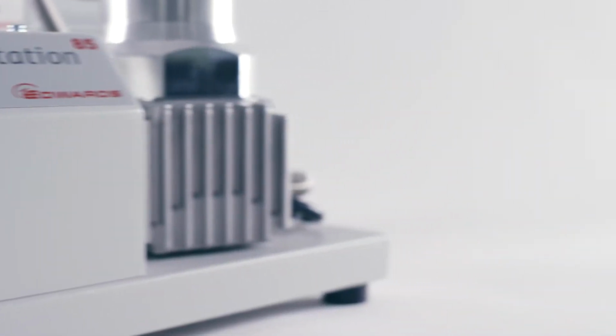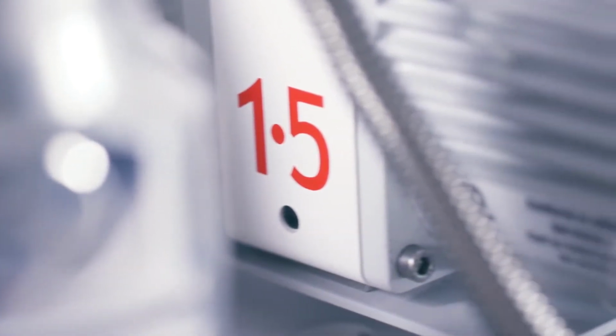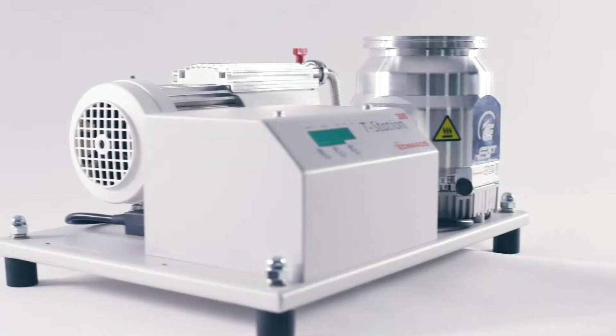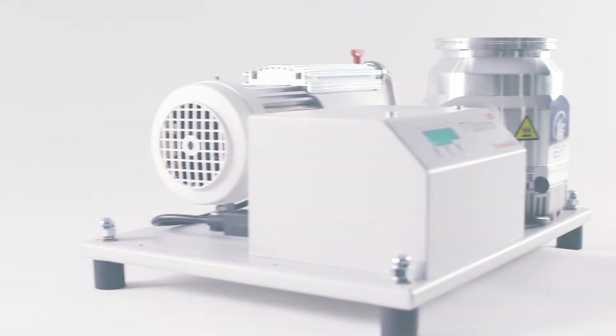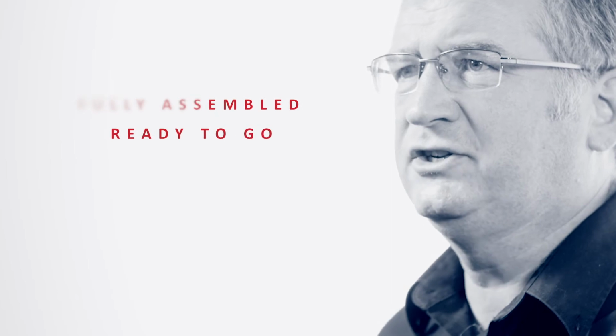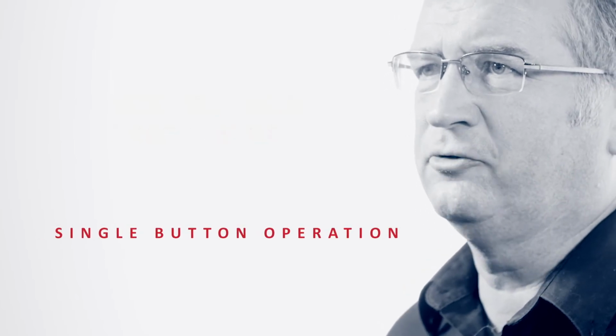T-Station is a cost-effective, compact unit. We combine the NEXT 85 or 300 turbomolecular pump and an Edwards turbo and active gauge controller with either the E2M 1.5 oil-sealed rotary vane pump or the dry XDD1 diaphragm pump. The T-Station is supplied fully assembled and ready to go with easy single button operation and a pumping speed of 47 to 300 litres per second.